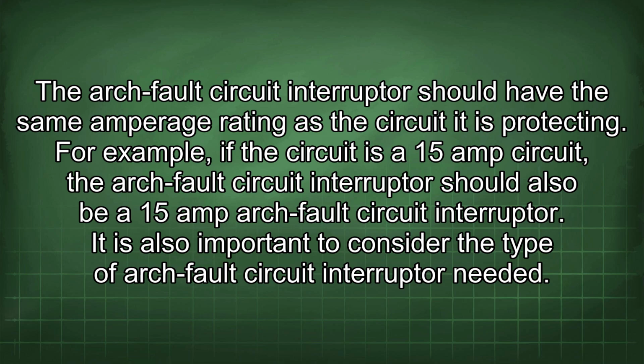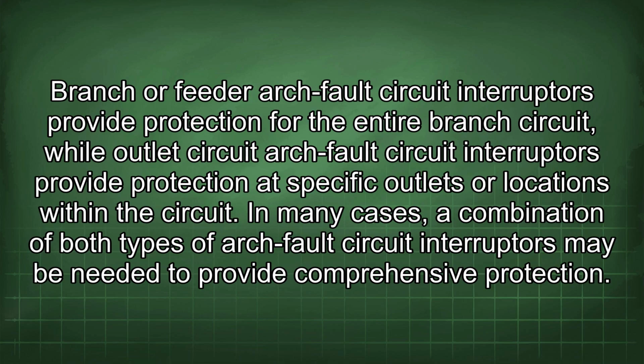It is also important to consider the type of arc fault circuit interrupter needed. Branch or feeder arc fault circuit interrupters provide protection for the entire branch circuit, while outlet circuit arc fault circuit interrupters provide protection at specific outlets or locations within the circuit. In many cases, a combination of both types of arc fault circuit interrupters may be needed to provide comprehensive protection.